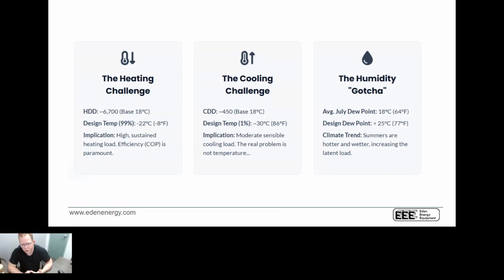So I've chosen my home as the example. So in my particular case, I live in Guelph. So the outdoor design temperature, typically we're looking at about -4 to -8. It depends on how bad, to what point are we doing to 1%? How are we going to look at what we're doing from a heating standpoint? So the nice part is even if we look at that design temperature to cover 99% of the year using just the heat pump with no backup heat, we can get a really high sustained COP. And again, that's every unit that we pay for. We want to get at least 3 units back for free because we're moving energy into the building, or in cooling, moving energy out of the building.